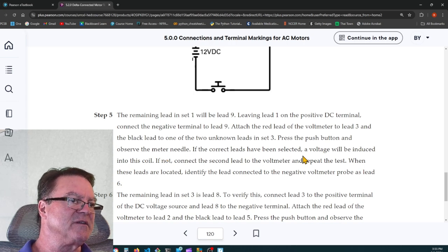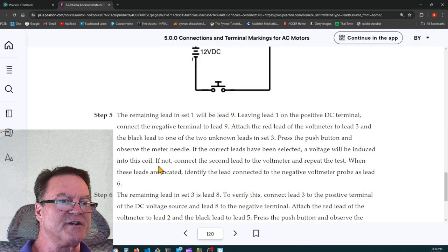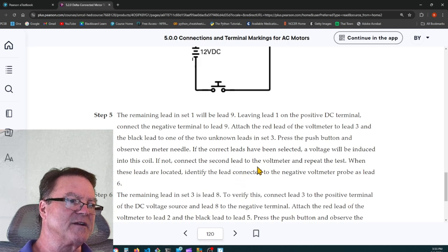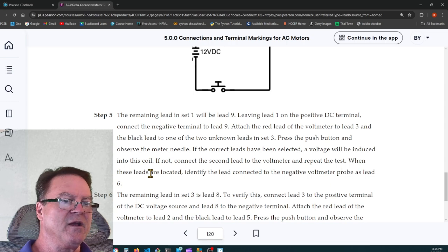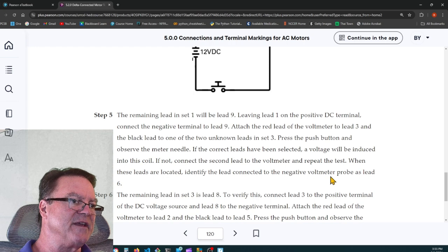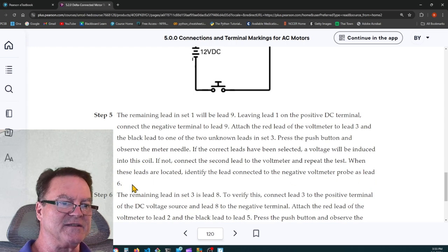If the correct leads have been selected, a voltage will be induced into this coil. If not, connect the second lead to the voltmeter and repeat the test. When these leads are located, identify the lead connected to the negative voltmeter probe as lead 6.